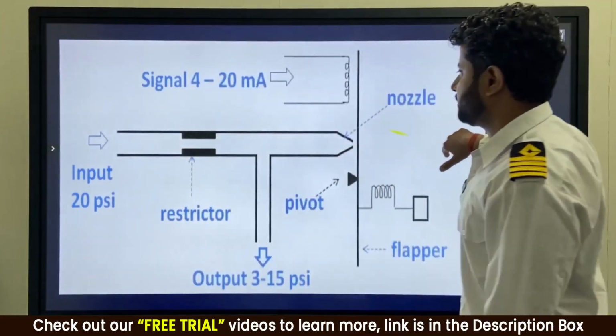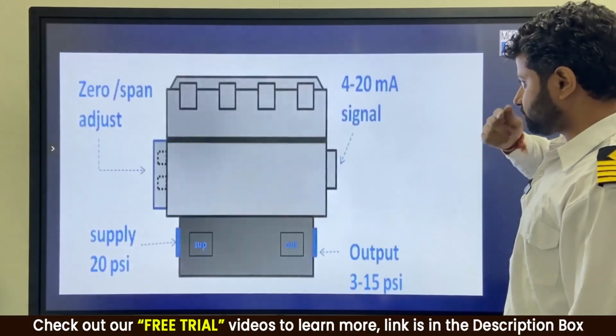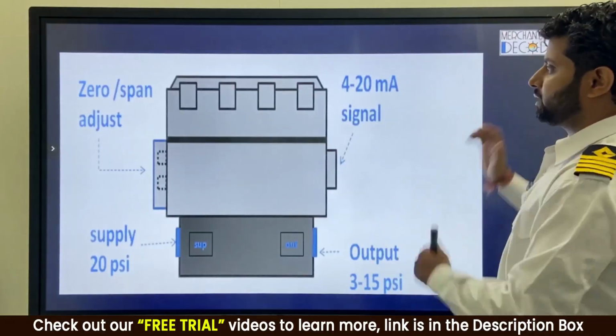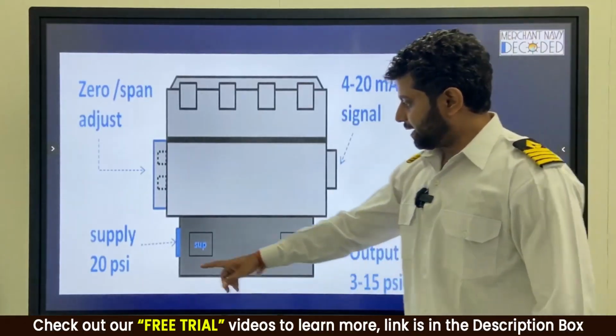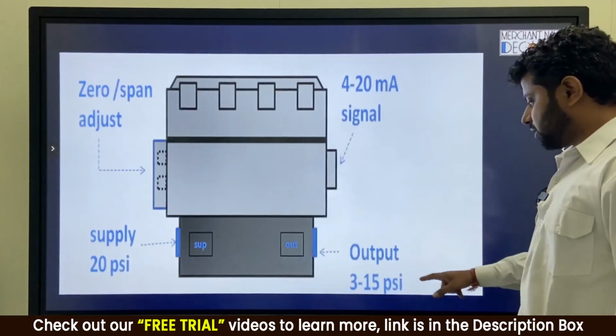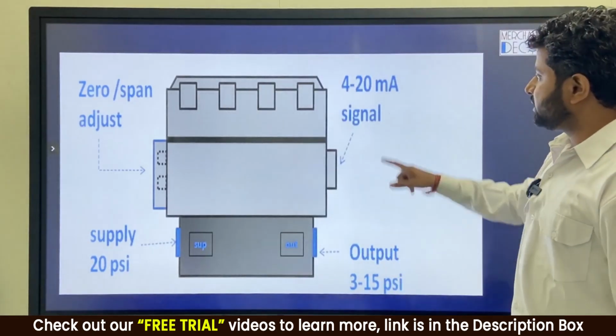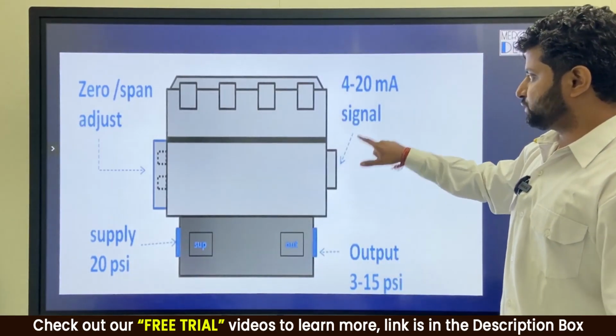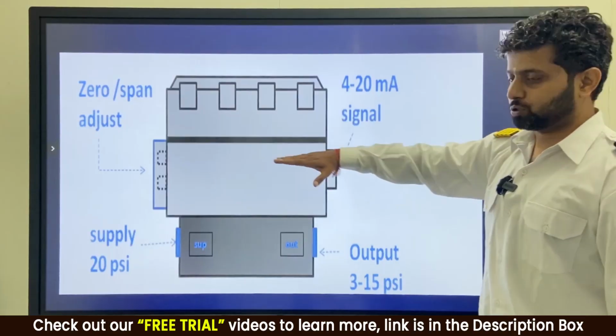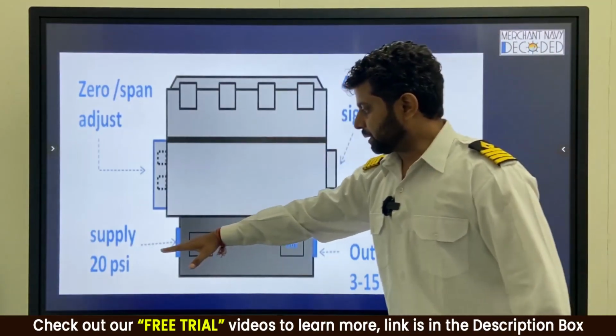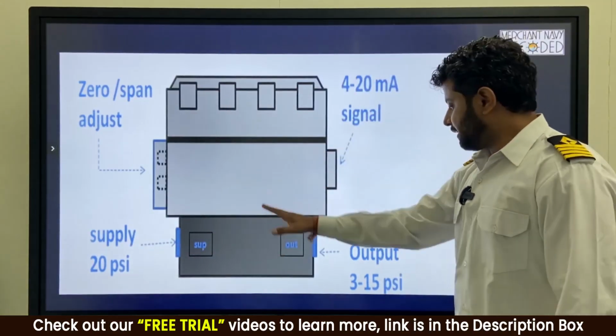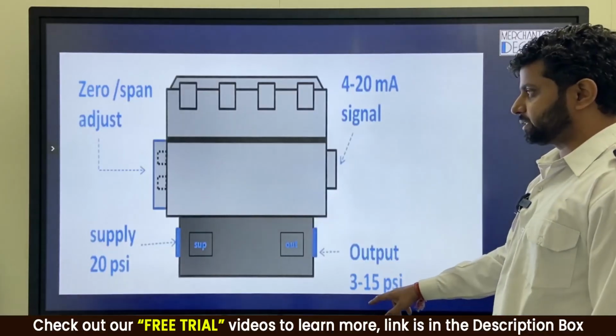So just let me show you how an IP converter looks. There is a supply of 20 psi, and the output coming is 3 to 15 psi. The signal which is coming into it is a 4 to 20 milliampere signal. It goes to the flapper, which moves up and down, the supply signal is going through the restrictor, and finally the output coming out is 3 to 15 psi.